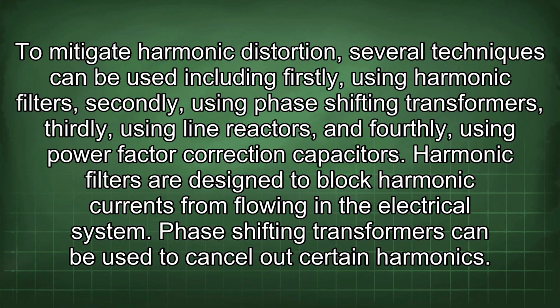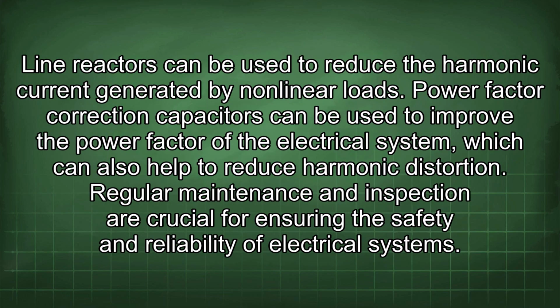Harmonic filters are designed to block harmonic currents from flowing in the electrical system. Phase-shifting transformers can be used to cancel out certain harmonics. Line reactors can be used to reduce the harmonic current generated by nonlinear loads. Power factor correction capacitors can be used to improve the power factor of the electrical system, which can also help to reduce harmonic distortion. Regular maintenance and inspection are crucial for ensuring the safety and reliability of electrical systems.